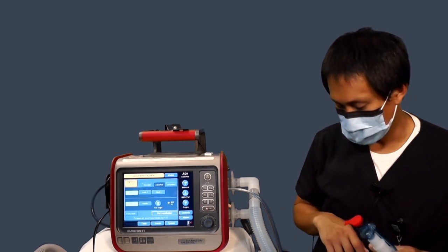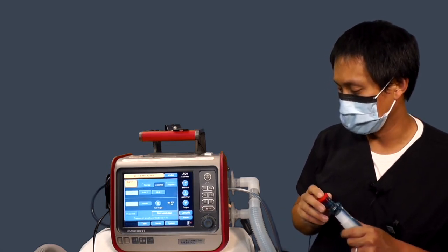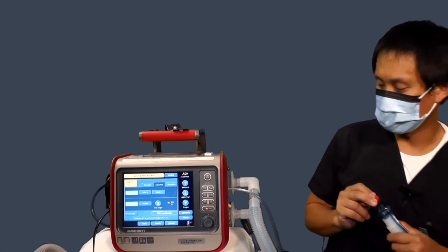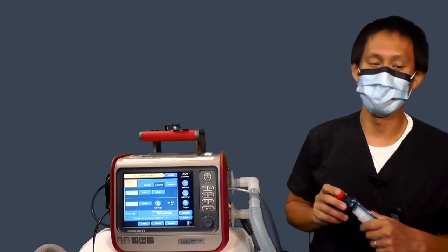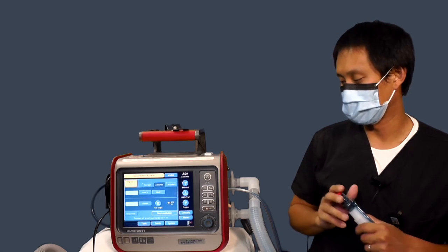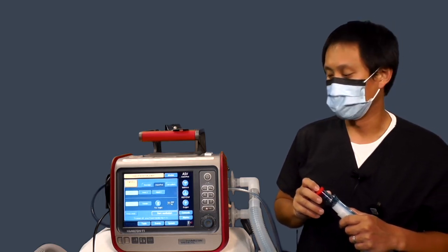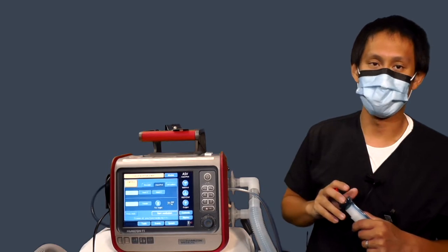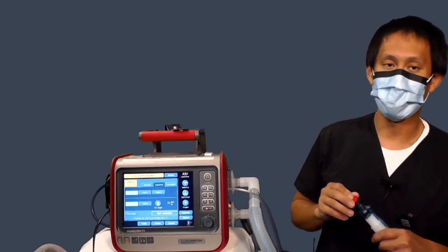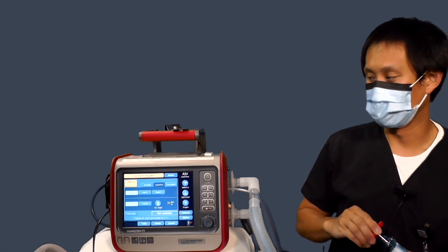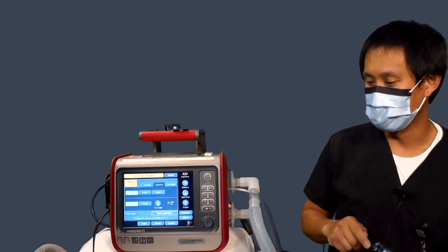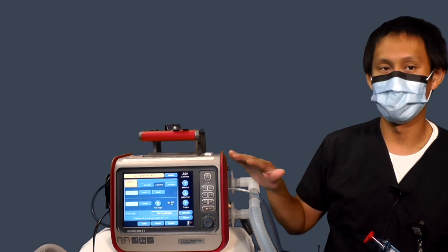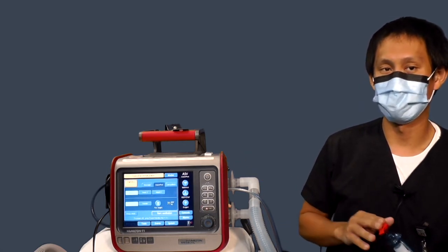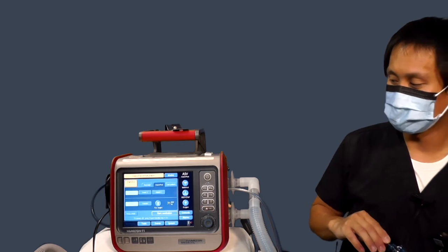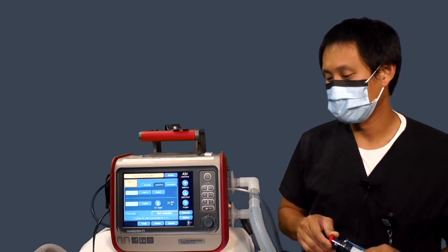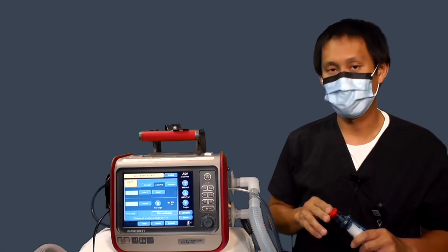as the circuits may be a little bit different, depending on if you're using the same circuit, where the difference may be very little, to if you're using a different circuit altogether, in which the calibration measurements may be different. The reason you do the calibrations is so that when you're running the vent, the measured and the output will be accurate to what your patient is doing. So your volumes and your pressures and your resistance and compliance will all be accurate.